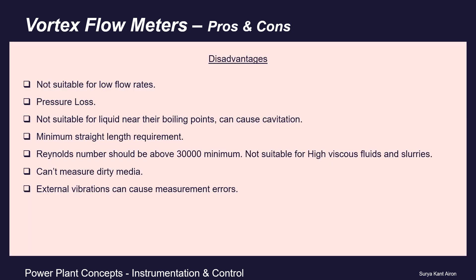Vortex flow meters do have disadvantages. First, they are not suitable for low flow rates, as low flows cannot generate vortices. However, this can be addressed by using reducers. Since flow rate equals area times velocity, reducing the cross-sectional area with a reducer increases fluid velocity for the same flow rate, making it measurable by the vortex flow meter.